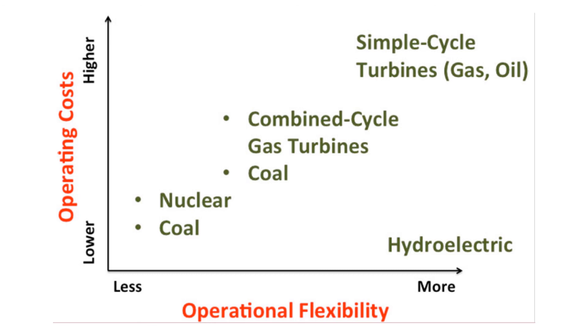This graph shows operation flexibility along the x-axis and operating cost along the y-axis for various power plants: coal-based, nuclear, coal gas, combined cycle gas turbine, simple cycle turbines (gas and oil), and hydroelectric. Hydroelectric power plants offer the most flexibility with the least operating cost. Gas turbine and oil plants are flexible but have higher operating costs. Nuclear and coal plants have less flexibility but lower operating costs. This summarizes the key points on capital cost and operating cost for power generation.